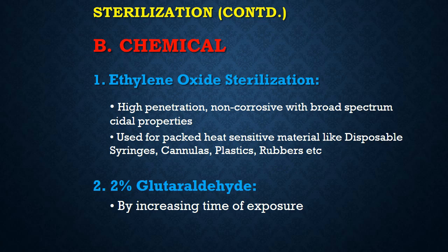After washing and cleaning, the instruments are placed and sealed in these packages, and these packages are then sent for ethylene oxide sterilization, and this ethylene oxide passes through the plastic and paper and sterilizes the instruments inside, so that the same instruments can be reused the very next day for your outdoor patients coming for treatment next day.